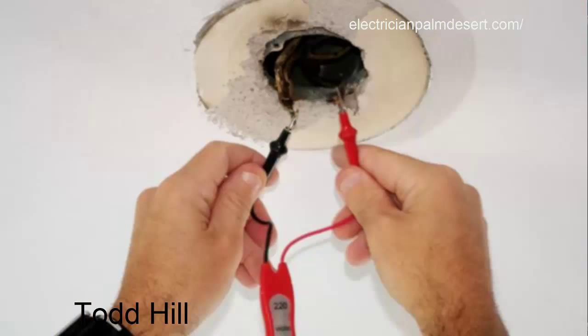Now, you can also retrofit, as you mentioned earlier, and it's a little bit more economical. You can just change out the light bulbs from, say, an incandescent recessed housing, put in a new light bulb. That's probably the simplest way to go. Great. And now, if they already have recessed lighting that doesn't work, what do you do? Well, if it doesn't work, we have to make it work before we decide to retrofit it to LED. So a little bit of troubleshooting here, find out if we've got power at the source, which would be the switch or the dimmer, find out if we've got power at the can or the housing, which is in your attic. If we got power there, generally it's easy to fix. If not, you have to take the next step and find out what it's going to take to get power there.